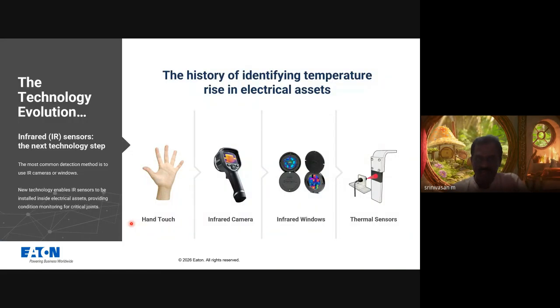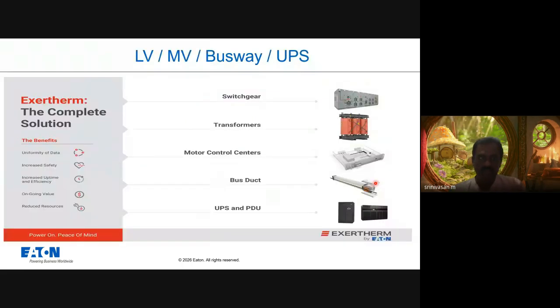I just want to show how the measurement of temperature and the technology have evolved. Initially, to see the temperature on the switchgear, people used to keep their hand on the non-current carrying metallic parts, like external doors or covers. Then people used the infrared camera. Then it evolved into infrared windows. Now we are reaching the level of thermal sensors, the same IR technology, infrared sensors, monitoring the temperature 24/7. By having this Exertherm point sensor, we can monitor the temperature in LV and MV switchgear, transformers, MCC, bus duct, UPS, and the PDU as well.